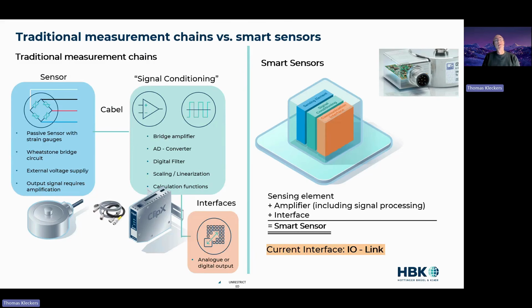Historically, we did work with sensors and signal conditioners, which amplified the tiny signal from the force sensors. Both were connected by a measuring cable to get the signals into our PLC or SCADA system. So we had altogether three components. We had a sensor, we had a cable, and we had a signal conditioner. Our smart sensors with IO-Link interface do the same thing, but they are just one device. So sensing element and amplifier system is all in one housing, in one system, and the interface is currently IO-Link, as mentioned before.